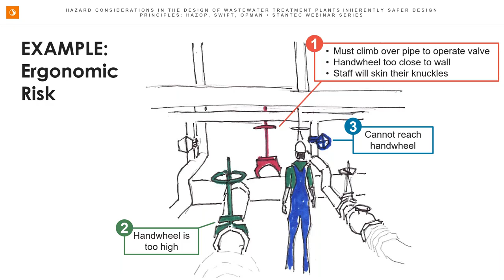Number 3 was even worse. There's just no way you could reach that valve in a safe manner without being in a very dangerous situation. Now you could say, why on earth did this even come into a design? Unfortunately this is more common than it should be, because the person designing back in the office isn't an operator and hasn't necessarily gone through the thought process of thinking about the person closing things like a manual isolation valve.